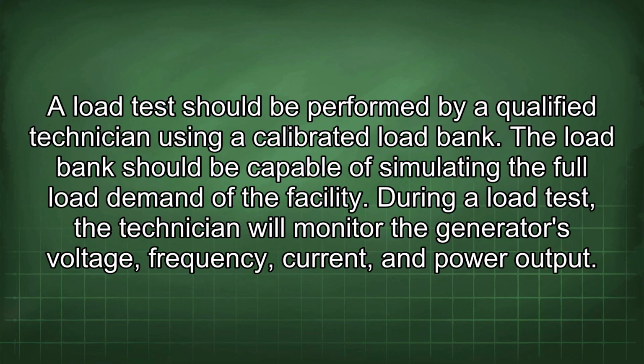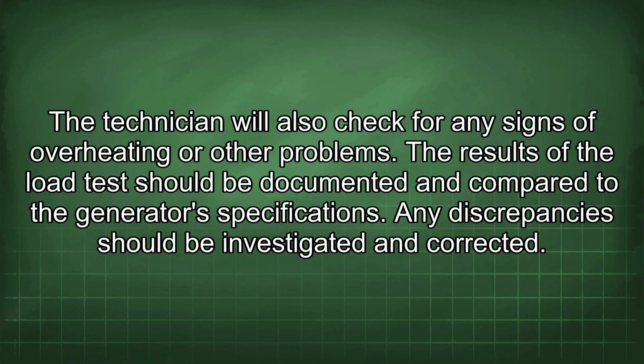A load test should be performed by a qualified technician using a calibrated load bank. The load bank should be capable of simulating the full load demand of the facility. During a load test, the technician will monitor the generator's voltage, frequency, current, and power output. The technician will also check for any signs of overheating or other problems. The results of the load test should be documented and compared to the generator's specifications. Any discrepancies should be investigated and corrected.